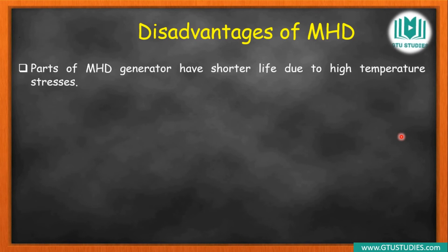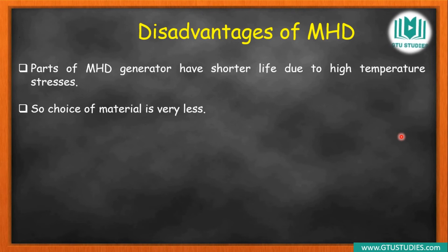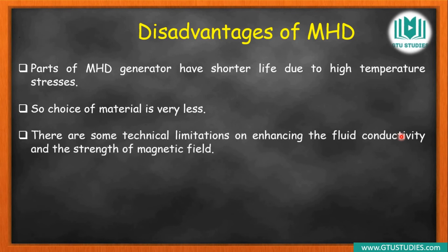There are also some disadvantages. First, parts of the MHD generator have a shorter life due to high temperature stresses, because the system operates at very high heat energy levels. Additionally, there are some technical limitations on enhancing the fluid conductivity and the strength of the magnetic field. Higher electrical conductivity of the fluid is needed to produce electrical energy efficiently, but increasing it technically has limitations.